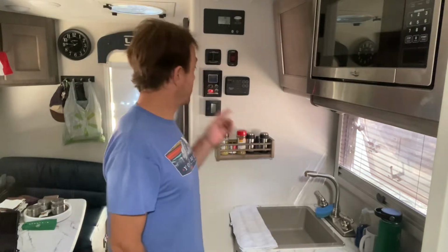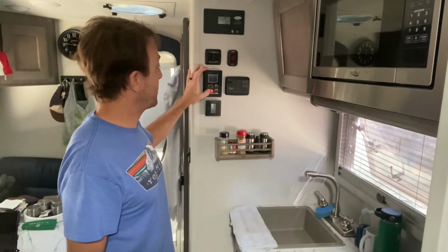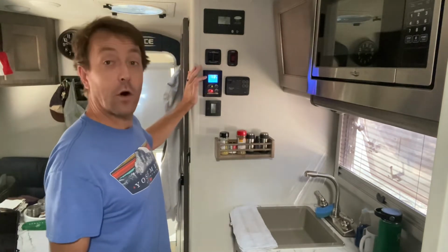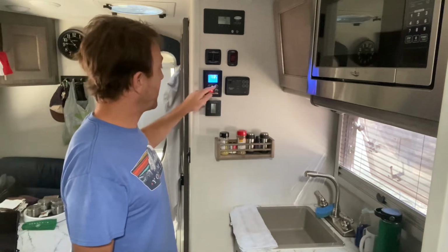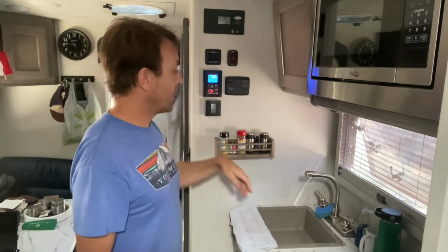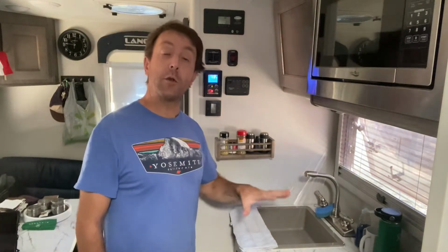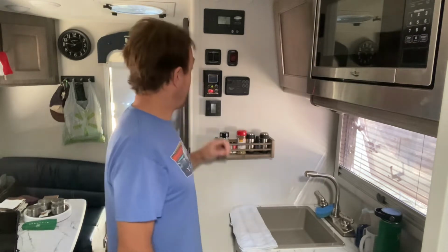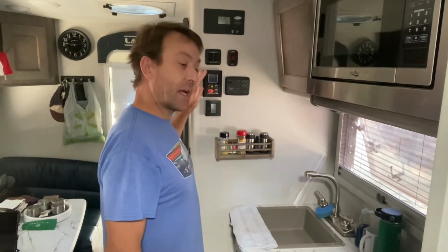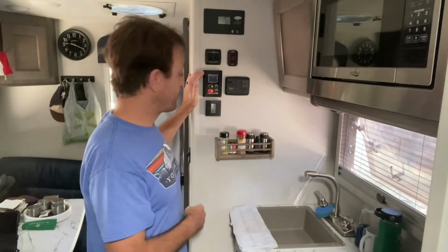Here's the control panel for the hot water heater. This is where we set the temperature. That's the power button. You can see I have it set for 112 degrees Fahrenheit. You can control the temperature here, and then this is just the power. So what would happen is when I would turn the hot water on, the hot water heater would not fire. It's an on-demand. When it operates, you can hear the gas because it's got a big blower, and you would get a beeping sound from here, and you'd get cold water out of here. The display would say E03.